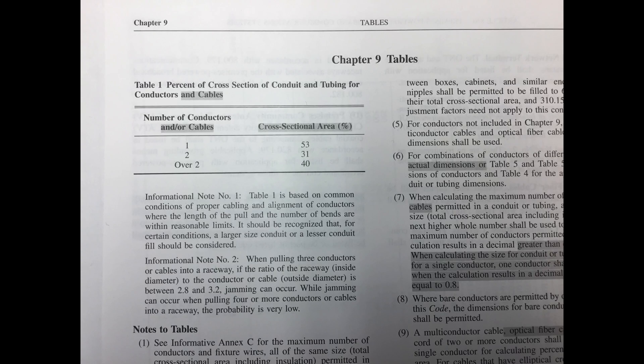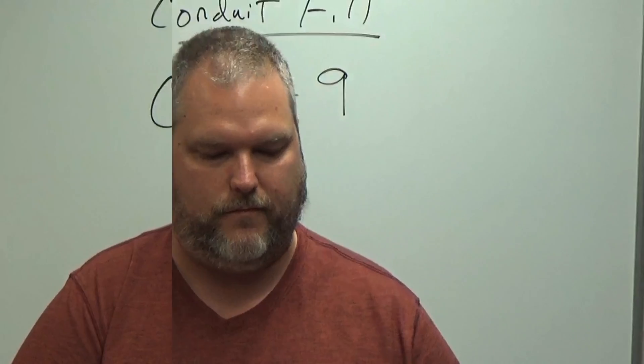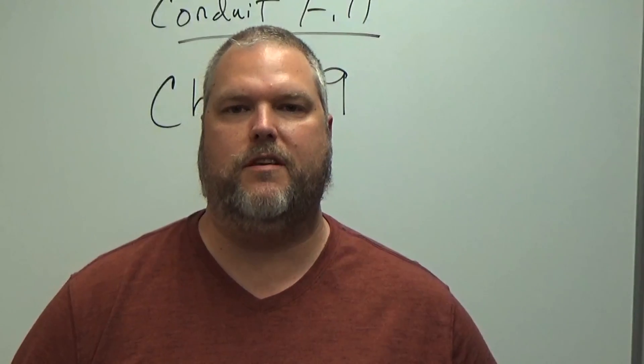As you can see in table 1, percentage of cross-sectional area of conduit and tubing conductors: one conductor is taken at 53%, two conductors at 31%, and over two is taken at 40%. So what do we do with this information?